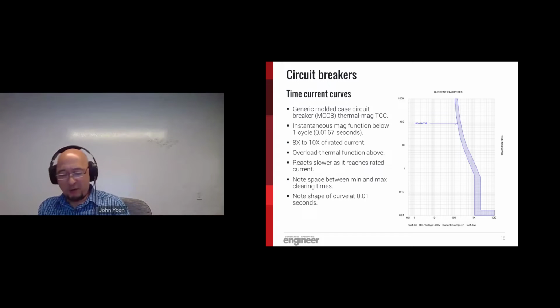So let's move on to how a thermomagnetic circuit breaker responds to various magnitudes of overcurrent. Here's a time current curve for a generic molded case circuit breaker. Again, we have a log graph of how this device responds to various levels of current. The blue band that you see represents the minimum and maximum trip thresholds for this breaker. Everything to the left of the curve is normal operating conditions, and the breaker will not open. And again, similar to a fuse, everything on the right side of it will open and interrupt the circuit. However, you can see that blue band is much wider than the fuse we were looking at before. The breaker is guaranteed to open somewhere within that band, but there's a lot more uncertainty regarding exactly where.